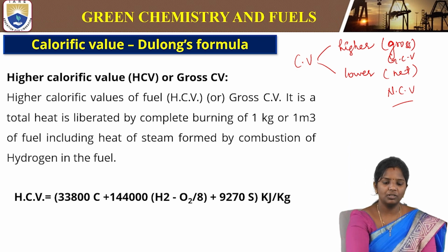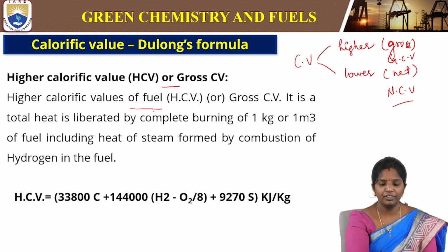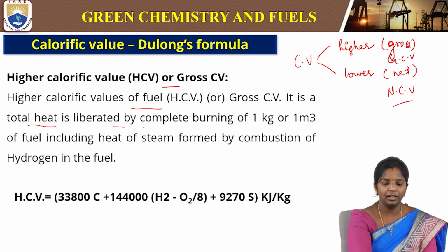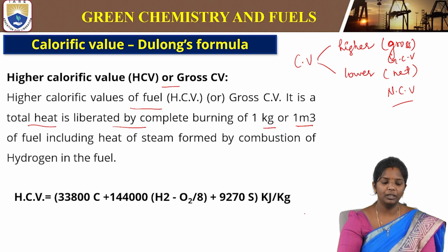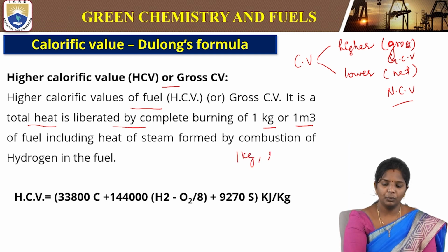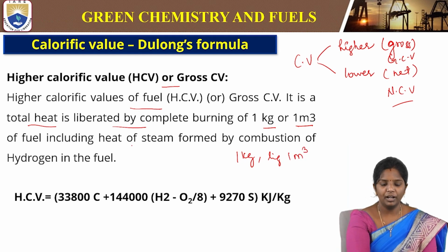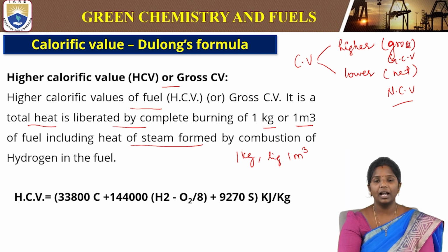So what is the GCV or higher calorific value? The higher calorific value or gross calorific value of a fuel is the total heat liberated by complete burning of 1 kg or 1 cubic meter of fuel. If it is solid, it is 1 kg, and for gas it is 1 cubic meter of fuel, including the heat of steam formed by combustion of hydrogen in the fuel. This gives the gross calorific value.